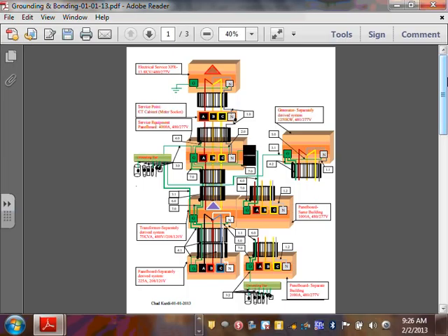Then from the CT cabinet, that could be on the wall or another box on a pad-mounted box, you're coming in with your 480/277 into your switchgear, switchboard, or panel board. Typically, right? That's what we bring in on a major power system. So that box here is my switchgear, switchboard, panel board, MCC, any service entrance equipment. We call them service entrance equipment, right? Cool. And these little things in between are supposed to be the conduits, guys.